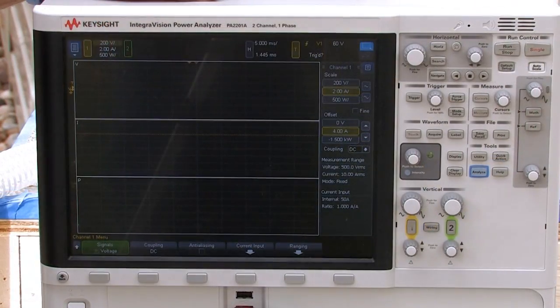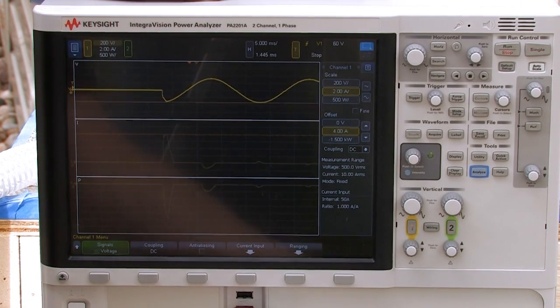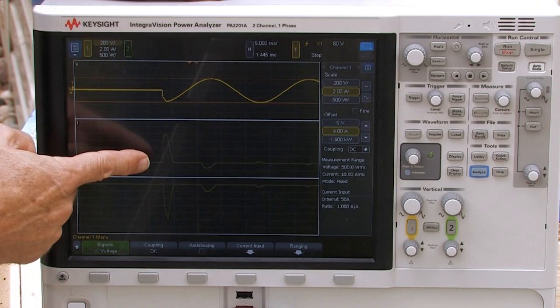Just like an oscilloscope, we're going to hit a single measurement, so we just come up here and press single, and now we have it triggered. We'll go ahead and get the water flowing through the pump. Now we'll energize the pump. And so here you can see the inrush current measurement.